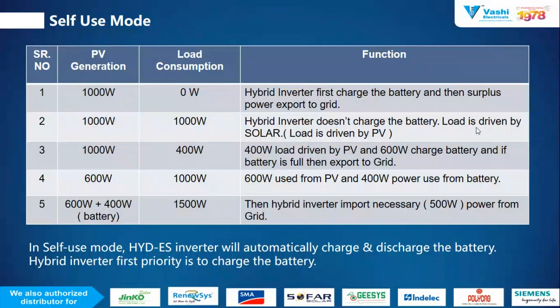Now consider the second condition, where the PV generation and load consumption are both equal. In this case, the hybrid inverter does not charge the battery. The load is totally driven from the solar, which means your load consumption is directly driven from the solar power. Third condition: when the PV generation is 1000 watt and your load consumption decreases from 1000 to 400 watt.